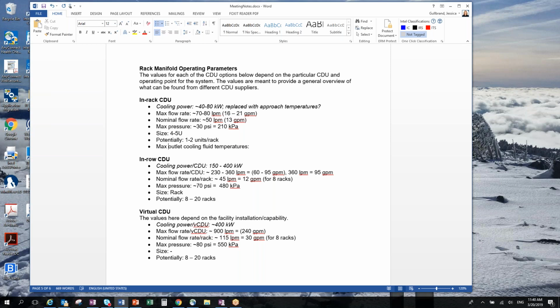For in-row CDUs, we can replace cooling power per CDU with approach temperature. What I found was 150 to 400 kilowatt CDUs, where max flow rates per CDU were in the range of 230 to 360 liters per minute, with a maximum pressure of around 70 psi. The size of it is a rack, and it could potentially cool 8 to 20 racks. So the nominal flow rate from that per rack would be about 45 liters per minute.